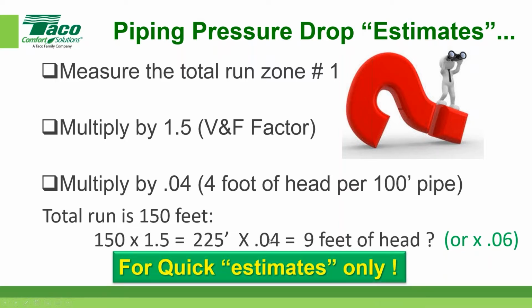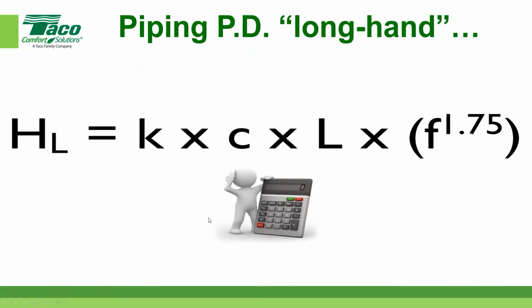Okay. Again, estimates only. Let's show you the calculation that a piece of software would use. You folks that are using anybody's software, let's say Radiant, because that's the most popular, and at the end of the design summary it says you have this many feet of head. Well, it's taking this information into consideration. We're solving for the head, that's what we're solving for, head loss. Okay. And we have this K number, times this C number, times this L number, times this thing in brackets here. We're not going to do this calculation. I'm just explaining what's in the background of the software that you're using, so you have a better idea of how it's coming up with this number.